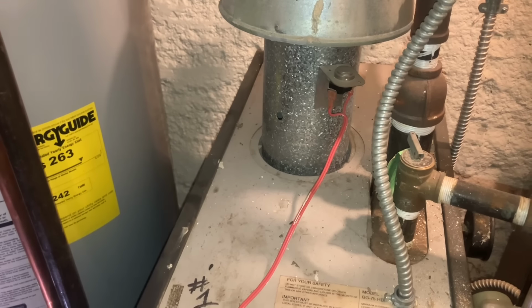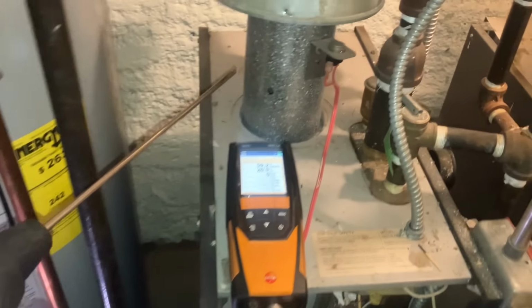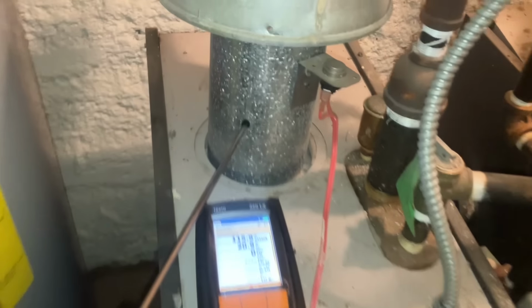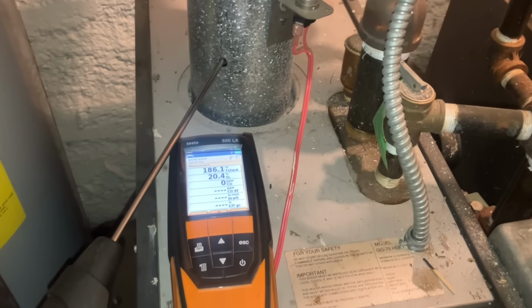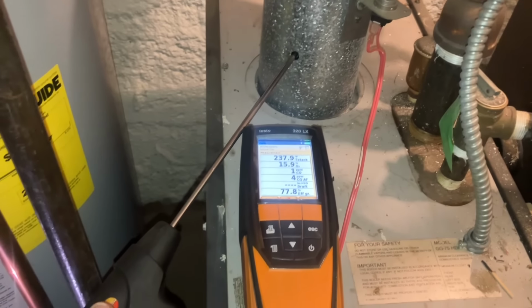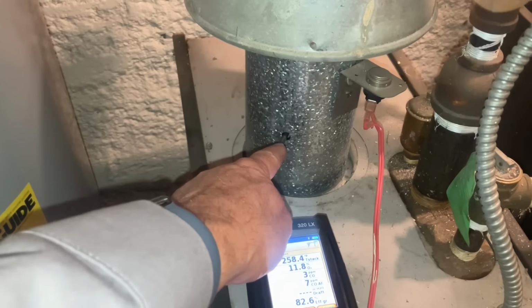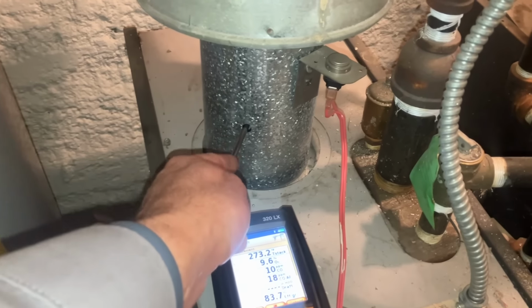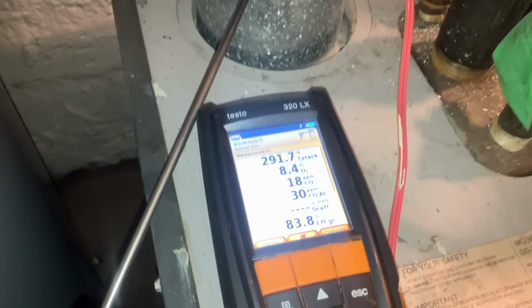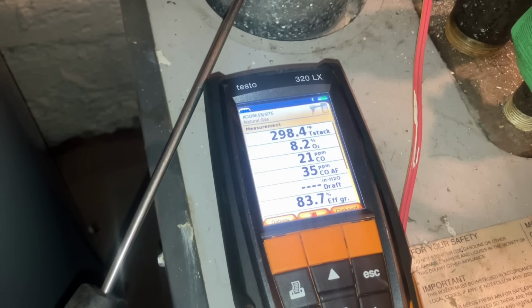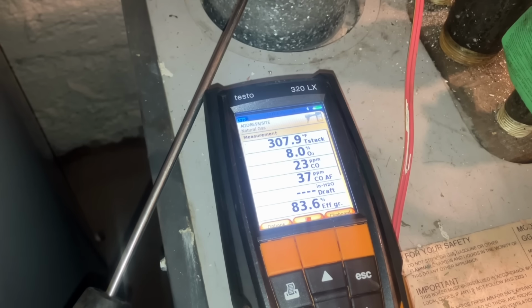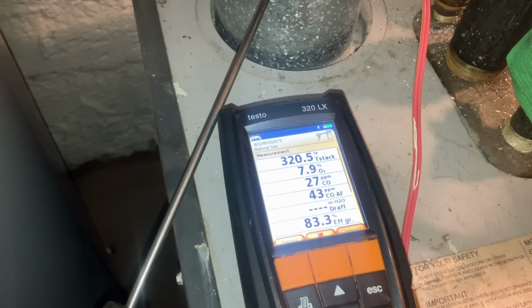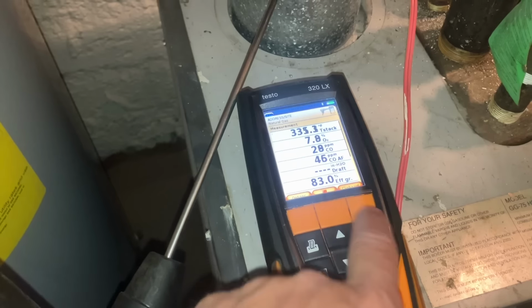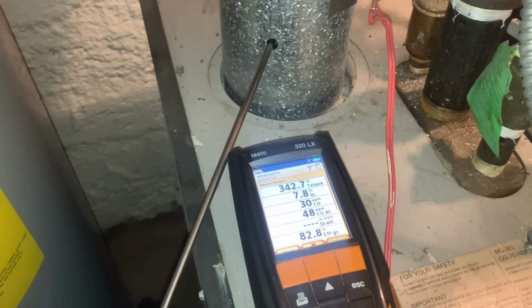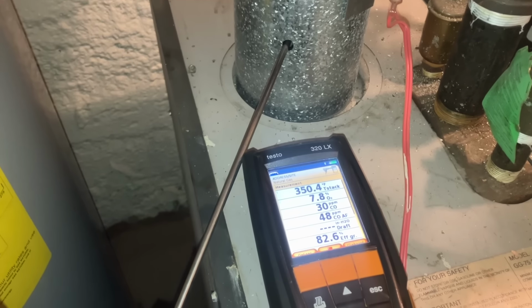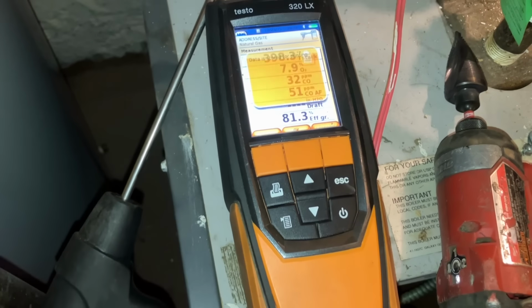Our combustion analyzer probe to test the exhaust gases. When we insert the probe, we want to be roughly in the middle of the flue pipe, and ideally in a position where it'll just stay there. Nice. If you make the hole just a little bit larger, you could take the little adapter that will hold the probe into the flue pipe. We're gonna let the boiler get to temperature, or as close to temperature as possible, which is 180 degrees. And as soon as we hit that, as soon as you see the boiler turn off, main valve close, we're gonna hit that clipboard button, and then we're going to save the results to the clipboard for printing. All right, we're gonna clipboard that.